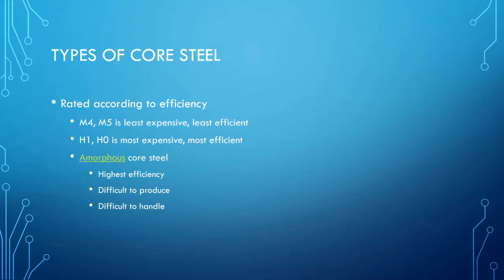Those core steels are more expensive. They are thinner, so more laminations can be put on the same size core, and more eddy currents can be reduced. Thereby, the heating is reduced, and that will make a more efficient, less lossy core.